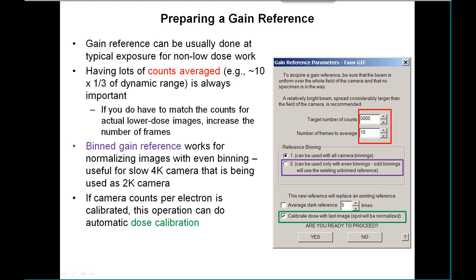One other thing to mention is preparing a GAIN reference. Taking a GAIN reference every day is just a good idea and keeps things working well, though it may not be necessary in some cases. The general recommendation is to do your GAIN reference at a higher exposure level — not what you need for low-dose work, but more of a mid-range exposure level. You need lots of counts averaged in these GAIN references to accurately measure the gain of the camera and not just the noise in your images. The recommendation is to have at least 10 frames with at least a third of the dynamic range of the camera.